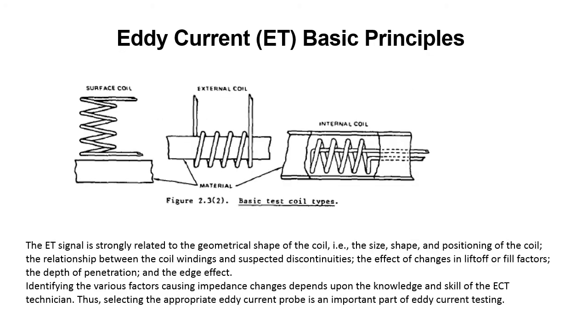The Eddy Current Testing signal is strongly related to the geometrical shape of the coil — i.e., the size, shape, and positioning of the coil — the relationship between the coil winding and the suspected discontinuities, the effect of change in lift-off or fill factors, the depth of penetration, and the edge effect. Identifying the various factors causing impedance changes depends on the knowledge and skill of the Eddy Current Testing Technician, thus selecting the appropriate Eddy Current Testing probe is an important part of Eddy Current Testing.